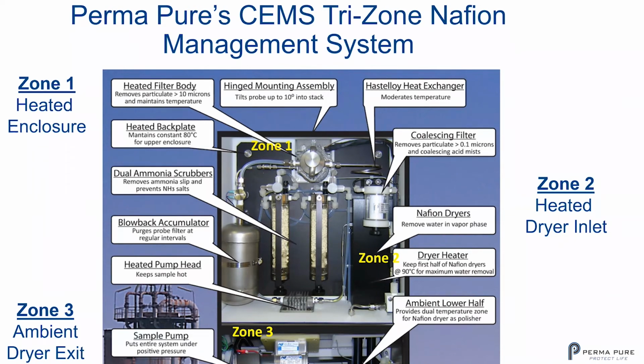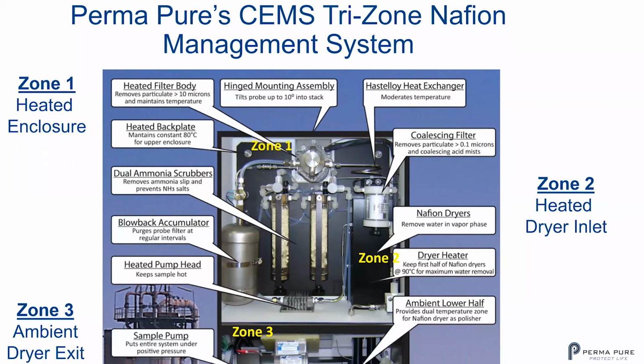The hot area is where the sample gas coming out of the stack is being processed and prepared for the dryer. The dryer is heated, and that hot, wet sample gas that is now cleaned goes through the dryer and exits cool and dry. The sample comes in at the center through the heated filter body. The heated filter body keeps that sample in the vapor phase and provides the first level of filtering, roughly to 10 microns.